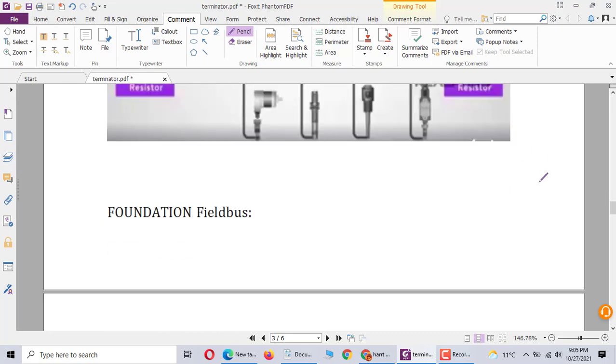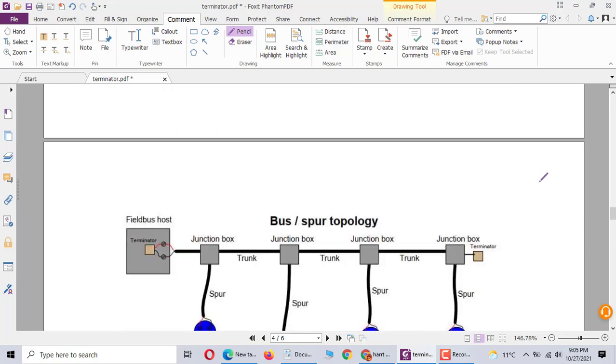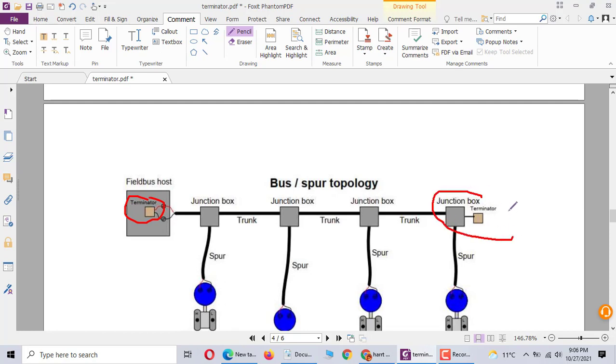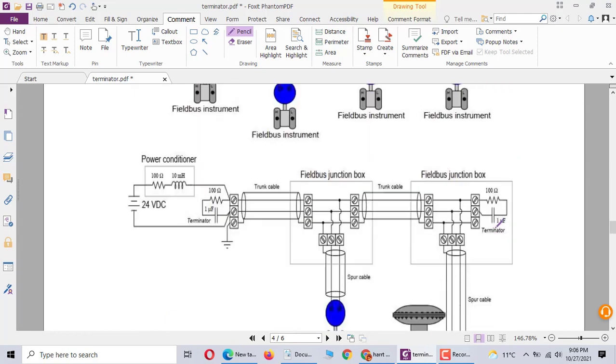Foundation Fieldbus installation, Foundation Fieldbus uses 100 ohm. The host uses termination 100 ohm. In the last junction box, use the termination 100 ohm. Here is 100 ohm, this is 100 ohm.